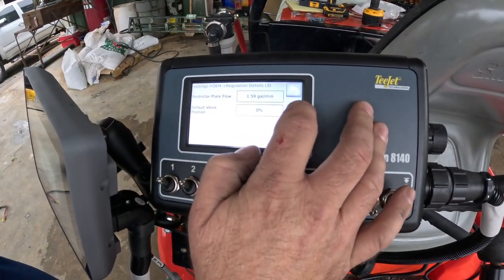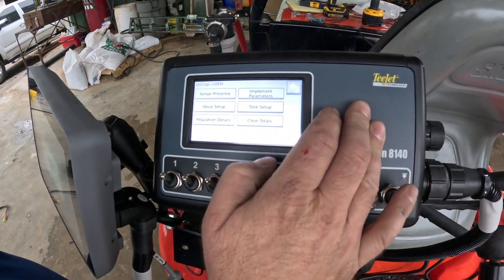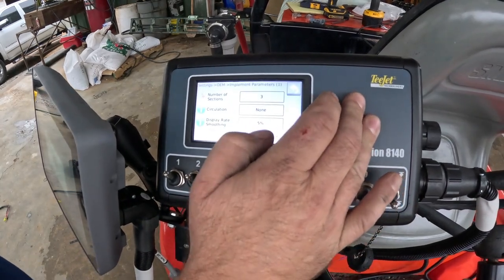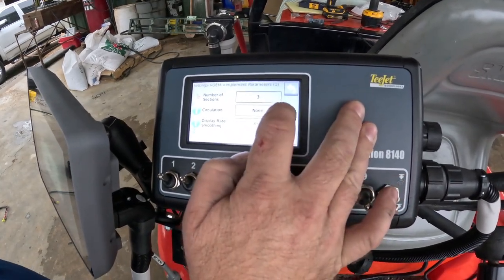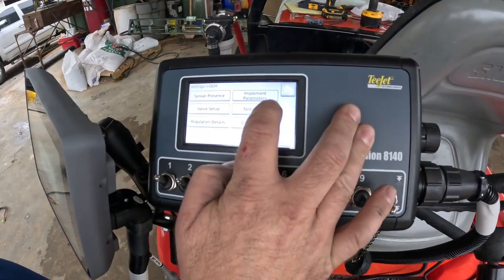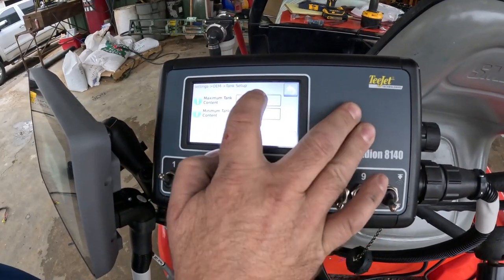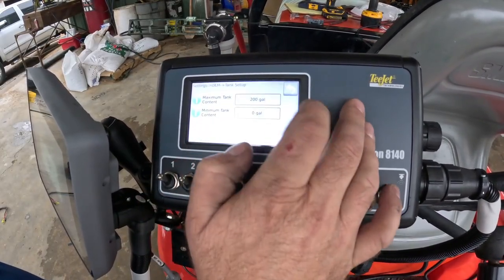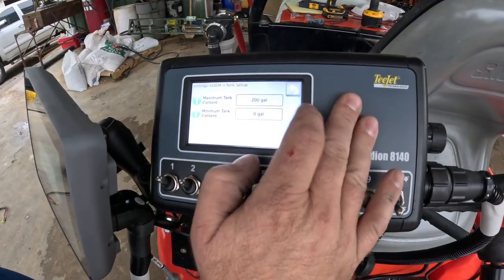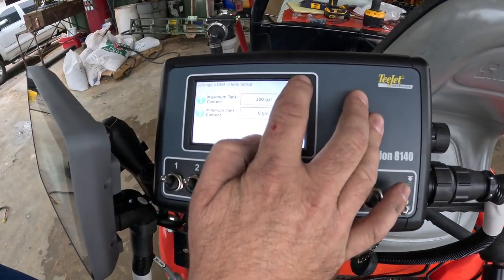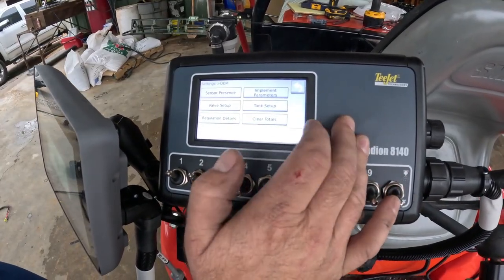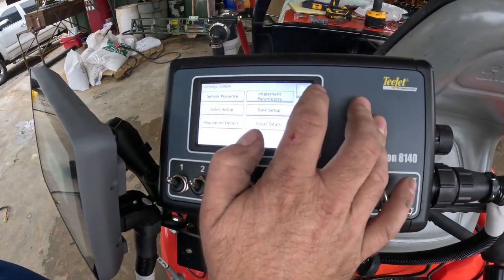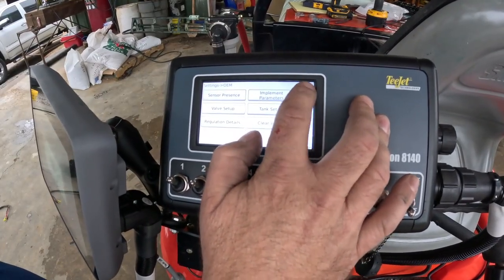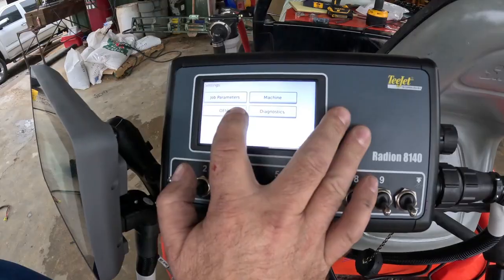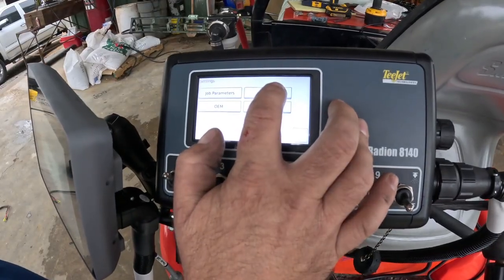So we're going to go back. Implement parameters. Number of sections, 3. Tank setup, 200 gallon. Minimum tank content, you can set that if you would like to have an alarm. Clear totals is not important right now because we don't have any totals. It's a brand new system. So that was in the OEM menu. So now we're going to go to machine.